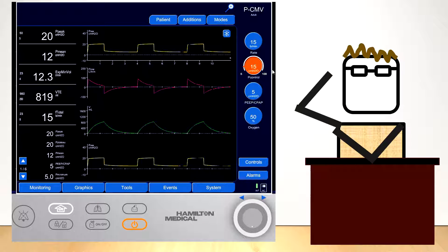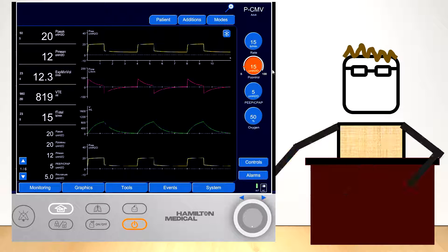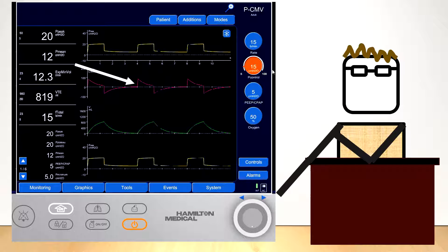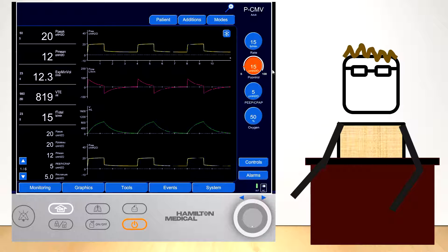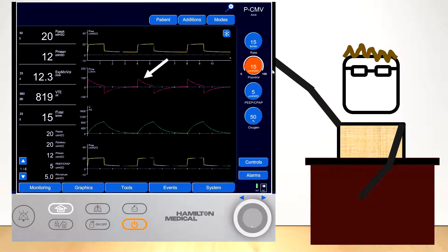When the patient triggers or assists a breath, or after a set period of time, the ventilator will rapidly increase air flow in the tubing until it reaches a set pressure in the circuit that had been set by the user. As the lungs inflate, the air flow in the ventilator tubing starts to decrease until the pressure is equal throughout the ventilator and the lungs.